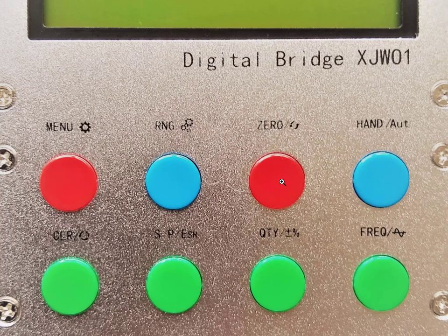This will start a calibration process in 3 different frequencies. When that's finished, you then short the probes together, and you're supposed to really do it with a 1 centimeter piece of wire, so that this emulates the connection of a component. So it's the component leads, typically about 1 centimeter long, half a centimeter each side.